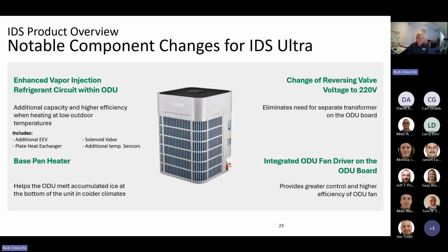Some of the enhancements to this unit, again, is that enhanced vapor injection to allow this unit to absorb heat from very cold outdoor ambient air and still move, in essence, that heat to the inside of the dwelling. It has a base pan heater built in, much like low climate ductless systems do. We've changed the reversing valve voltage from 24 volts to 220 volts in this unit, allowing for defrost transition to be a little stronger in cold weather scenarios. And this unit has a superior integrated outdoor unit fan driver, allowing that fan to operate at a wider range to absorb more heat out of that very cold ambient outdoor air.